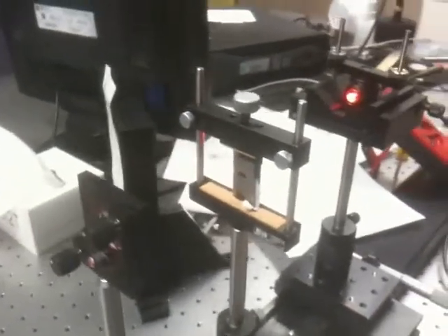In the last lab we used both methods, where you take measurements both inside focus or both outside of focus, and then there's another method where you can take one measurement inside focus and then another one outside, but I'm going to use the first method because it's more practical in this situation to take measurements both inside focus.